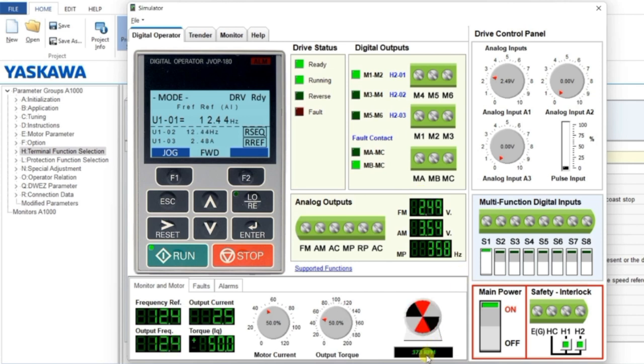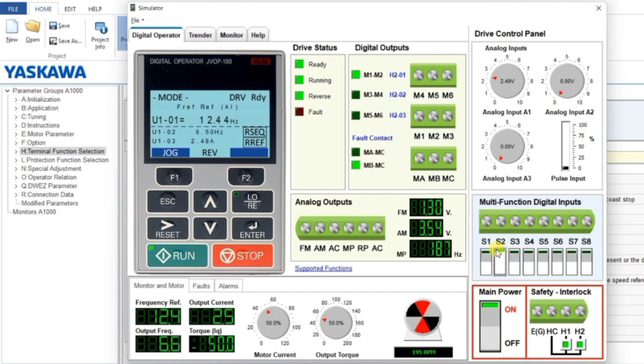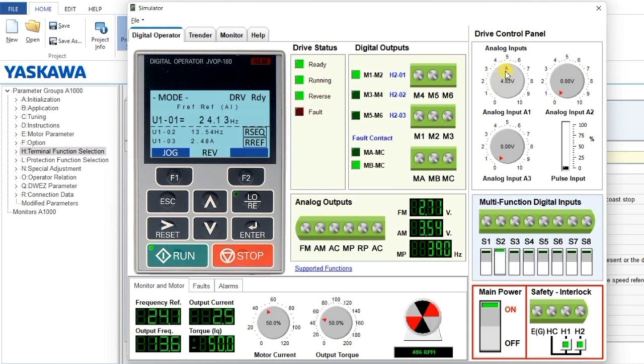The motor is running as per the analog input value. To run in reverse direction, first stop the motor and let it reach the stop condition. Then click the S2 terminal. You can see the direction is now reversed, indicated both on the keypad display and the direction indicator. You can also change the analog input value to adjust speed.